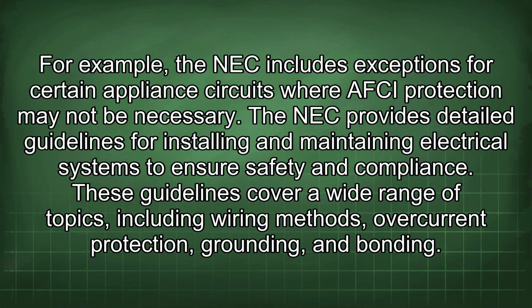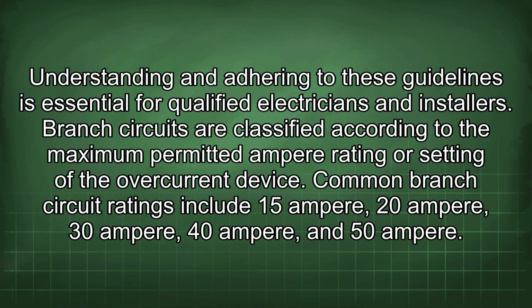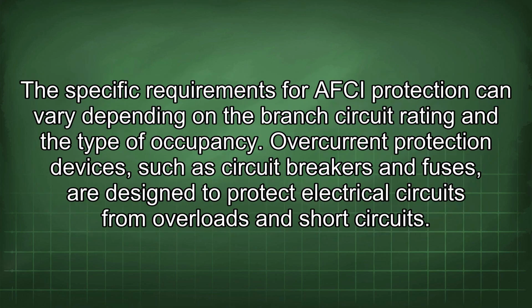The NEC provides detailed guidelines for installing and maintaining electrical systems to ensure safety and compliance. These guidelines cover a wide range of topics, including wiring methods, overcurrent protection, grounding, and bonding. Understanding and adhering to these guidelines is essential for qualified electricians and installers. Branch circuits are classified according to the maximum permitted ampere rating or setting of the overcurrent device. Common branch circuit ratings include 15 ampere, 20 ampere, 30 ampere, 40 ampere, and 50 ampere. The specific requirements for AFCI protection can vary depending on the branch circuit rating and the type of occupancy.